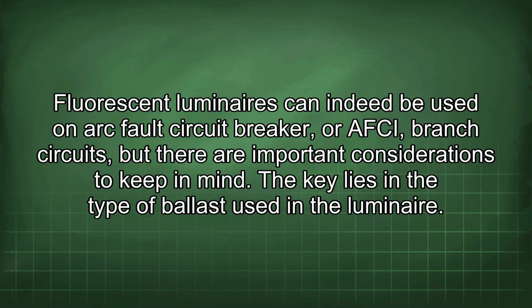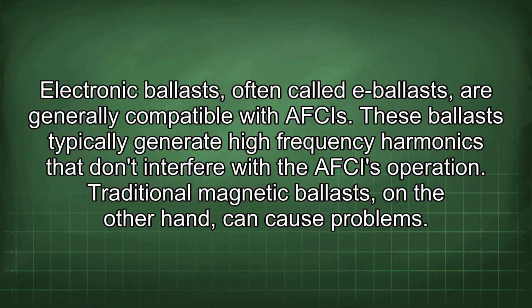Fluorescent luminaires can indeed be used on arc fault circuit breaker, or AFCI, branch circuits, but there are important considerations to keep in mind. The key lies in the type of ballast used in the luminaire. Electronic ballasts, often called e-ballasts, are generally compatible with AFCIs. These ballasts typically generate high-frequency harmonics that don't interfere with the AFCI's operation.